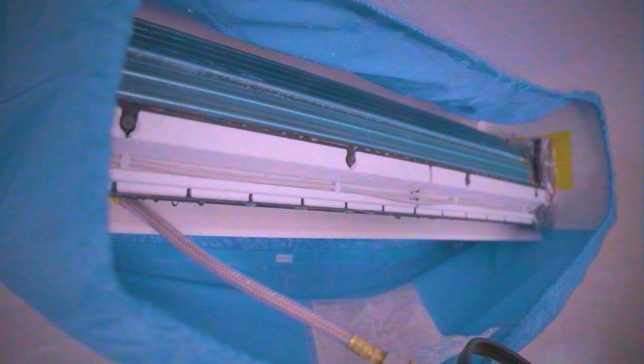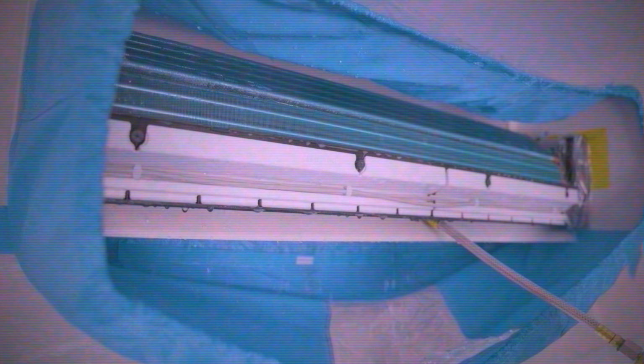Next, clean the blower wheel. Access the blower wheel through the louver openings using an extended sprayer head. Spray directly into the blower wheel, making sure that it spins. This ensures the entire surface gets coated and helps break up debris. If using a higher pressure spray, spray upward through the louvers to help spin the wheel.